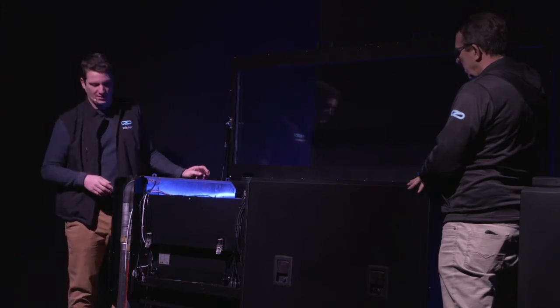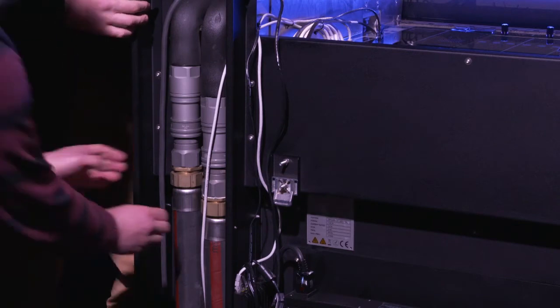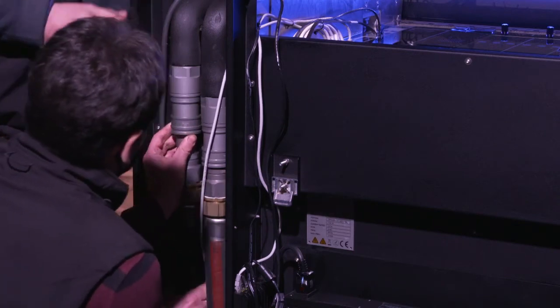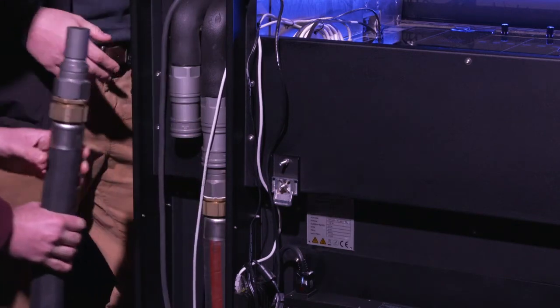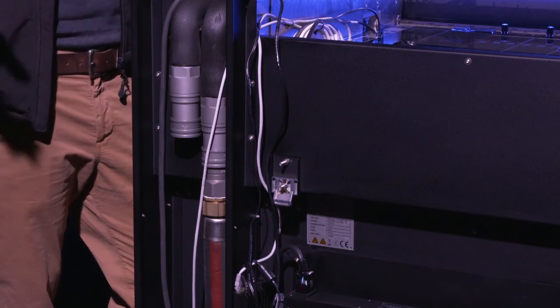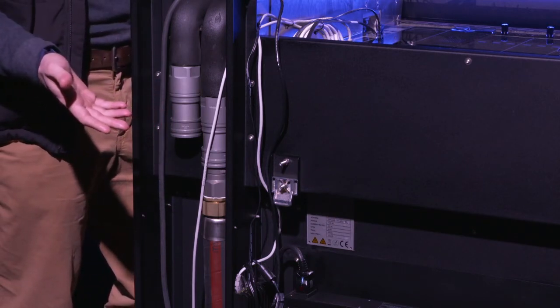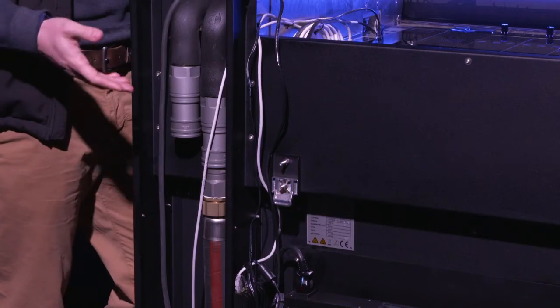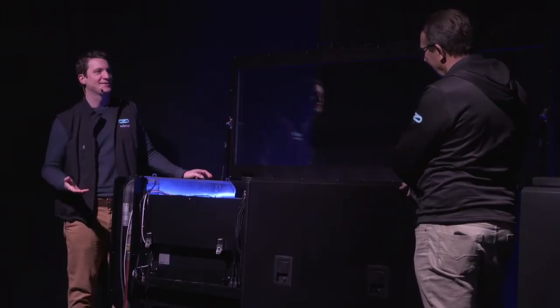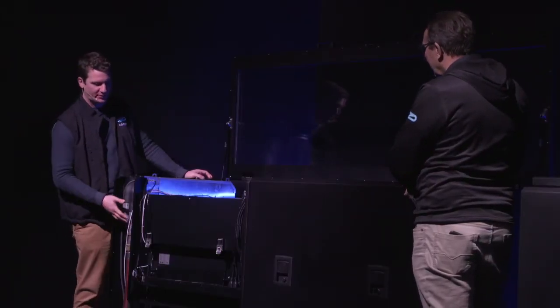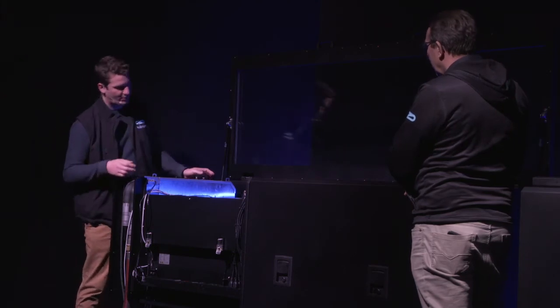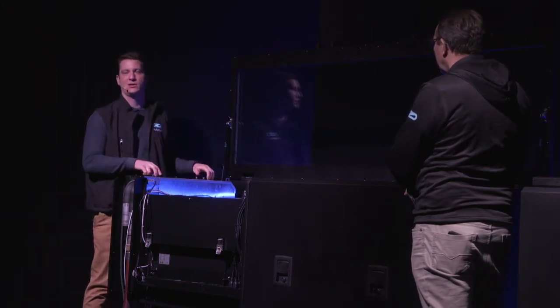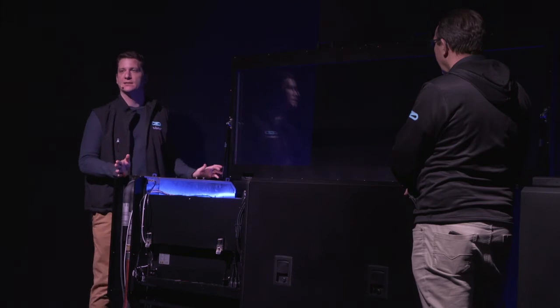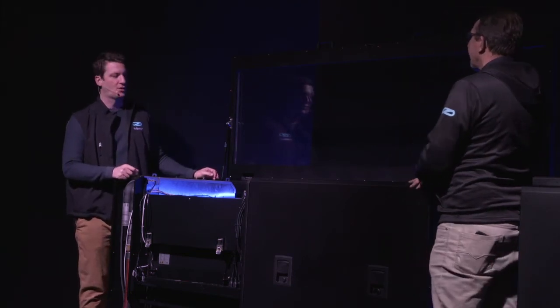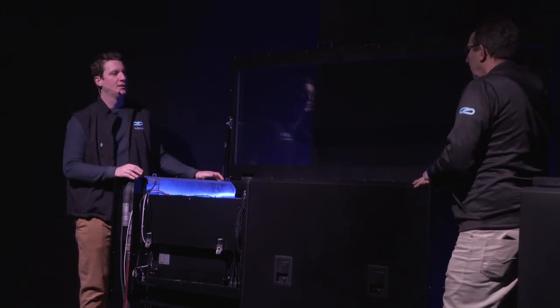So Edgar, if you can help me disconnect one of the hoses so that we can show these hoses are pressurized. They supply water to the system in real time, and so that's how quick it is to disconnect one of these hoses. Obviously, we'd take both of them out, and we would be able to extract a CDU in less than 5 minutes. The whole system is designed for that.